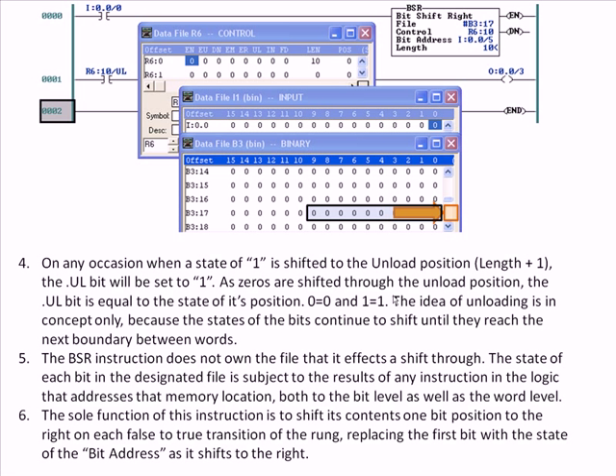The BSR does not own the file it affects. The state of each bit in the designated file is subject to the results of any instruction in the logic that addresses that memory location, both at the bit level and the word level. The sole function of this instruction is to shift the contents of its file one bit position to the right on each false-to-true transition of the rung, replacing the first — that is, the highest — bit with the state of the bit address. For B3:17 with length 10, bit 9 is the highest bit, so it loads into bit 9, then shifts toward bit 0, and when it shifts out, the unload bit comes on.